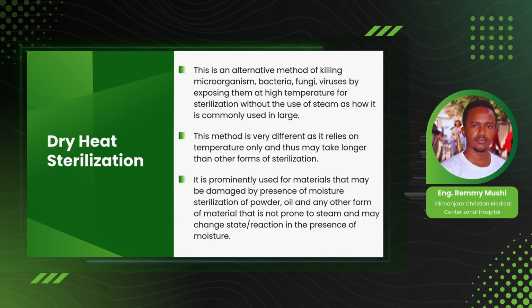So what is a dry heat sterilizer? A dry heat sterilizer is a medical equipment that is used to kill microorganisms such as bacteria, fungi, and viruses by exposing them to a higher temperature without the use of steam, as is commonly used in most cases. This method relies on the use of temperature as well as time in order to ensure there is maximum sterilization in the load or in the material or in anything that you are planning to sterilize.